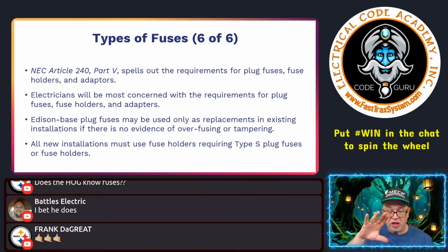What you will find is pieces of equipment that still have an integral Edison base into the switch. It may be a separate device for a piece of equipment that's built with a switch, which is the disconnect, and it'll have a built-in Edison base. That is fine, because that is a newly listed piece of equipment. Nobody's creating panels generally anymore. I can't think of anybody that would use Edison base, okay?